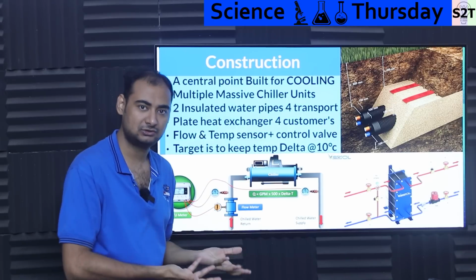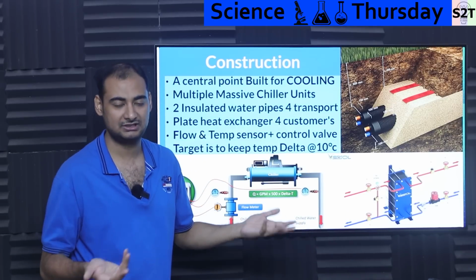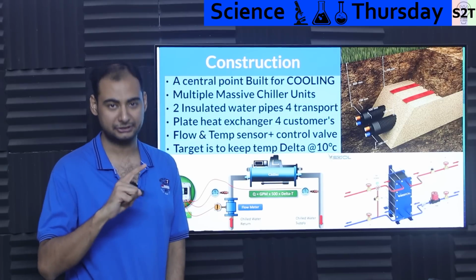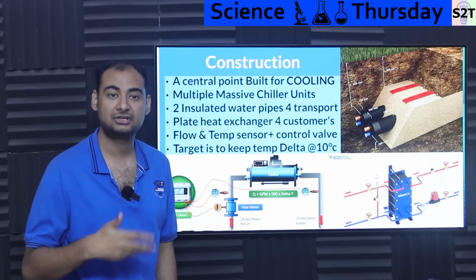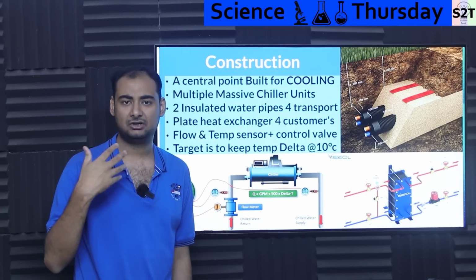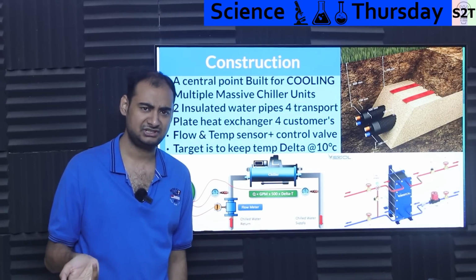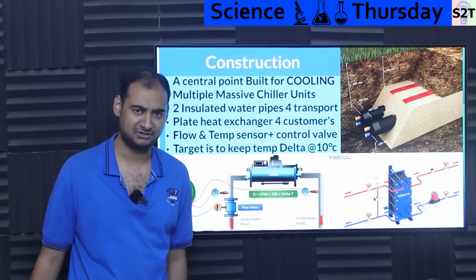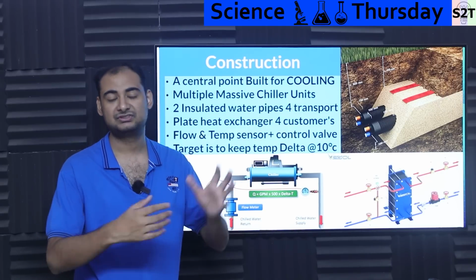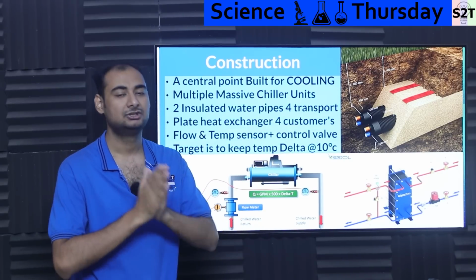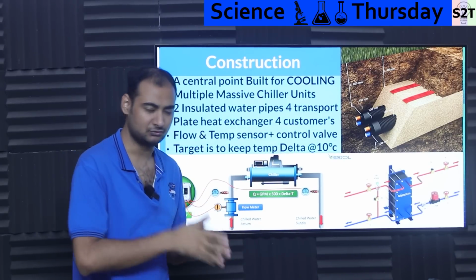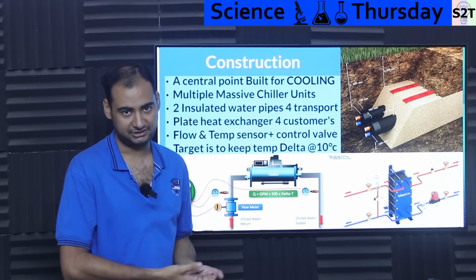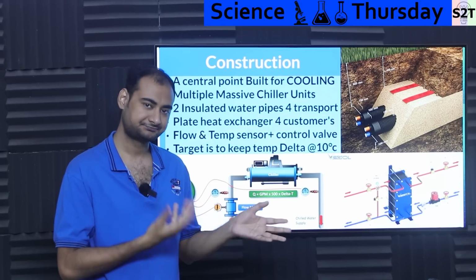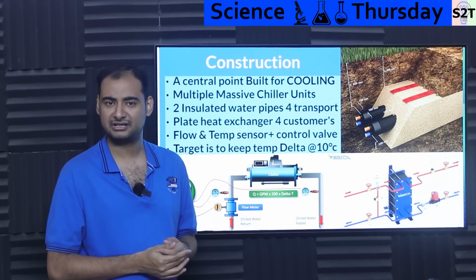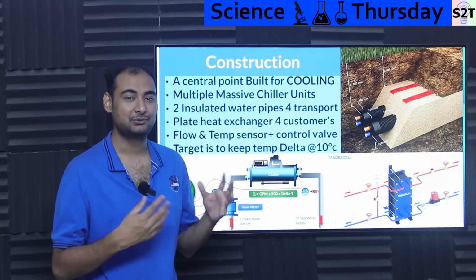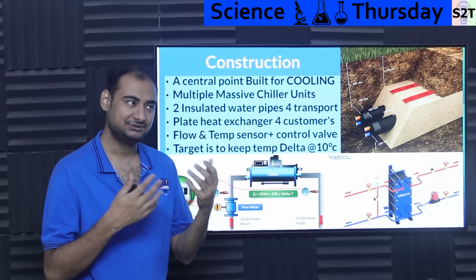Now, how does the customer do the cooling? Okay, they have a block that can get cold. What do you do with that? You run your coolant through it, which again could be distilled water, could be distilled water with antifreeze, or could be oil also. But I've never seen anybody using oil, because why would you? It's a lower thermal capacity. And then you send that cold fluid through what we call air handling units. Most large buildings have that, and that's how you get your cooling. Or you can send it through air conditioning, which again is not recommended, but it can be done. If you really want very low temperature, you can do that.